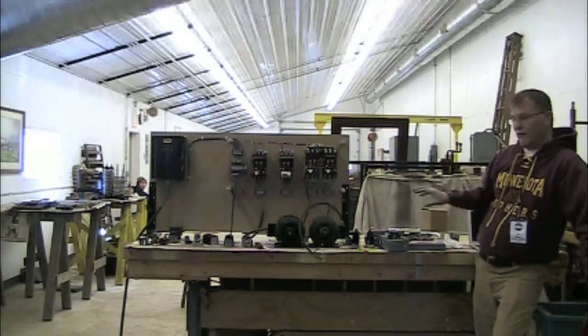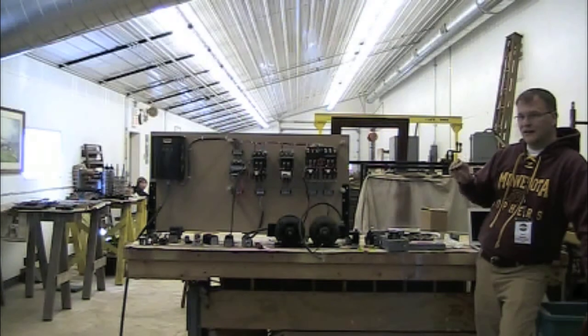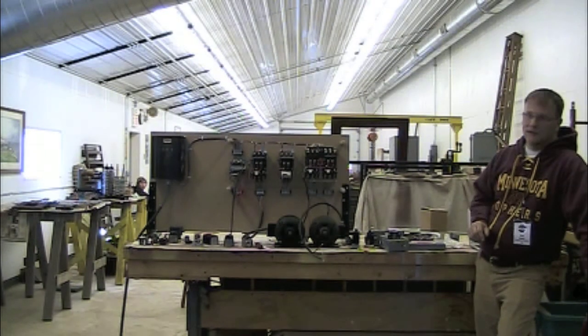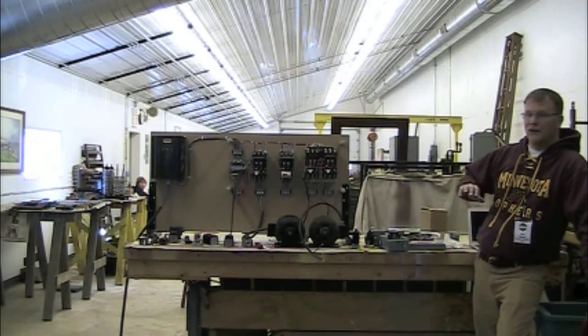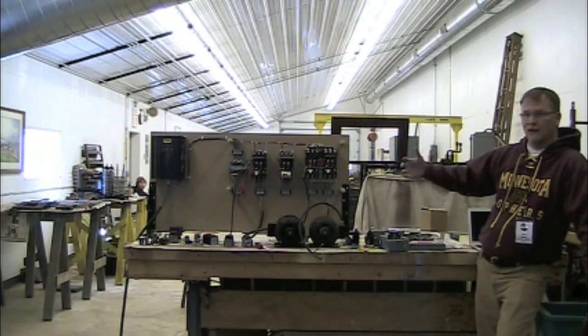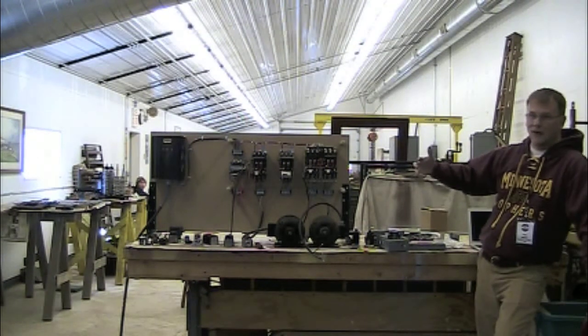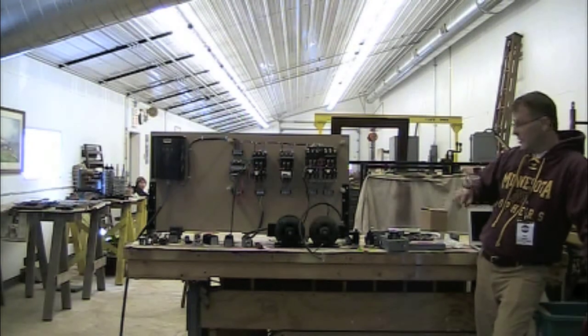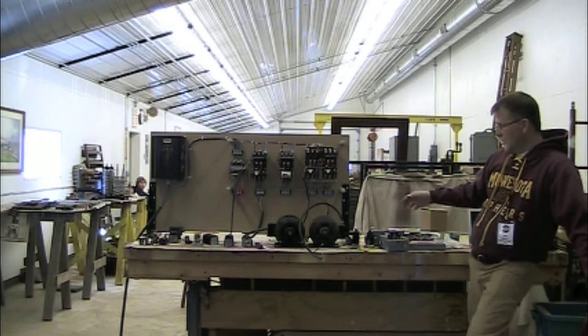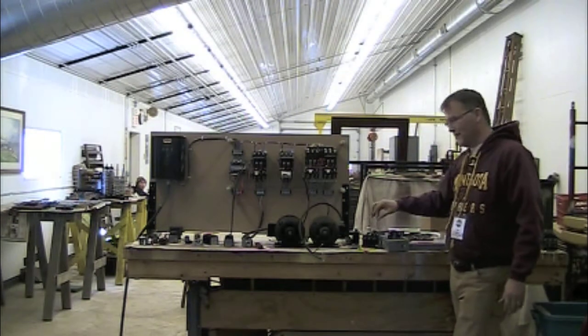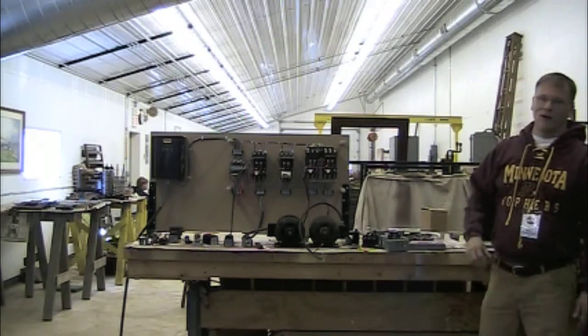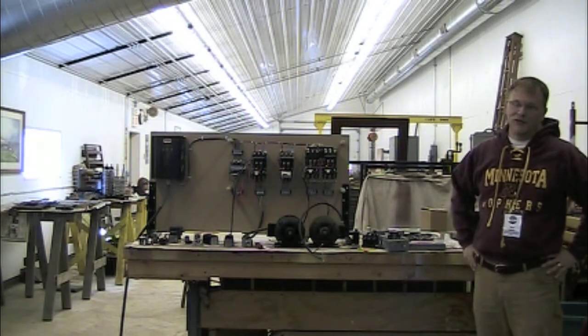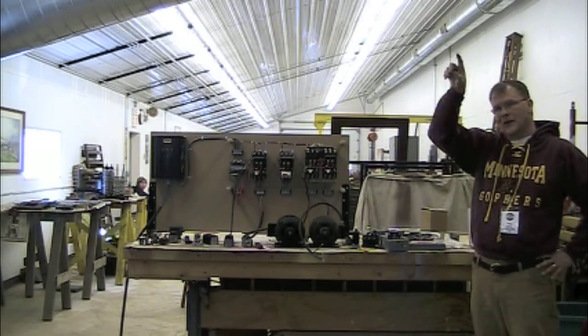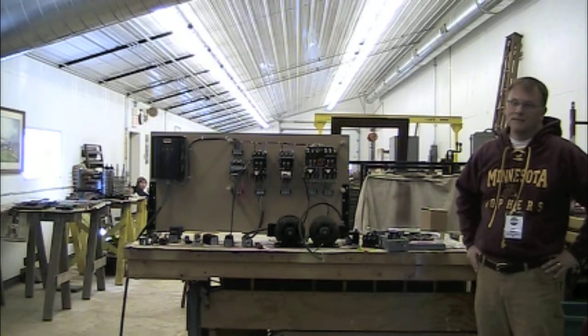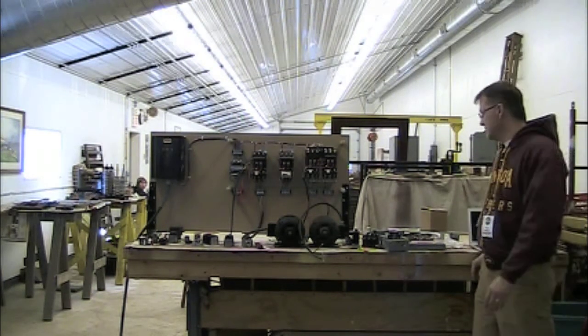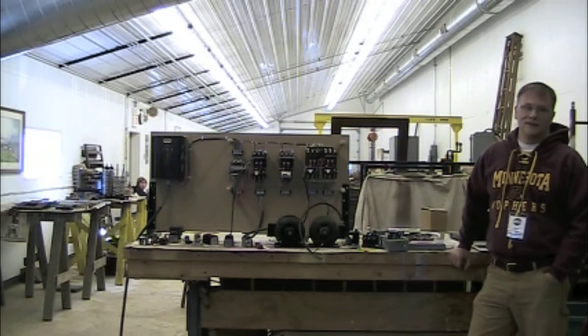So the overload side of this is actually designed to mimic the heating characteristics of a motor. It allows you to run at overload for a long period of time, in terms of minutes. What is it, Class 10 or whatever, it has to be able to run for 10 seconds at 600% of its rated value. And the curve is very nonlinear. Any other questions so far?